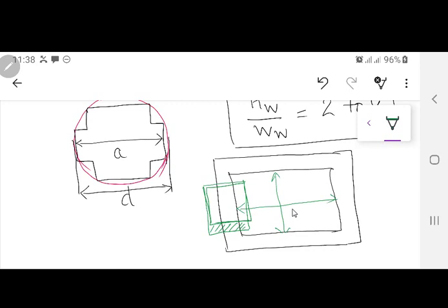This time you will again redesign the winding, either by changing the size of the conductor or by changing the orientation of your conductor, so that it takes the full length. When it covers the full length, then you will have an oil duct, and on that oil duct you will do the HT winding. So keeping the height and the width of the window fixed has constraints, since you are going to use a selected number of conductors which will fix your constraints.